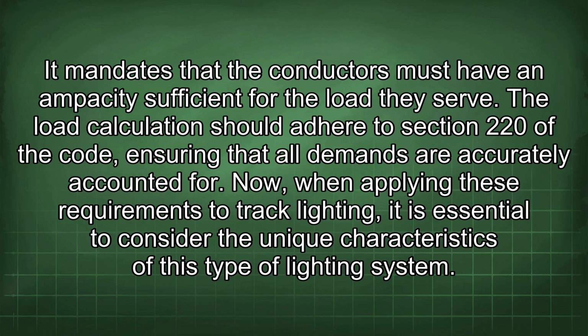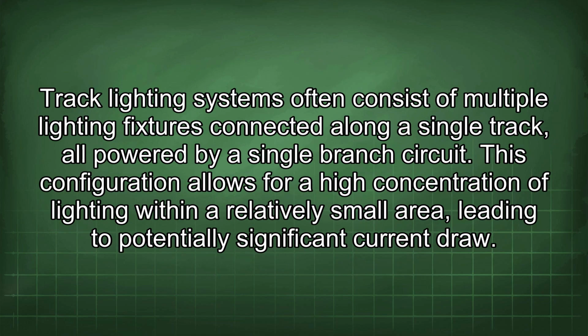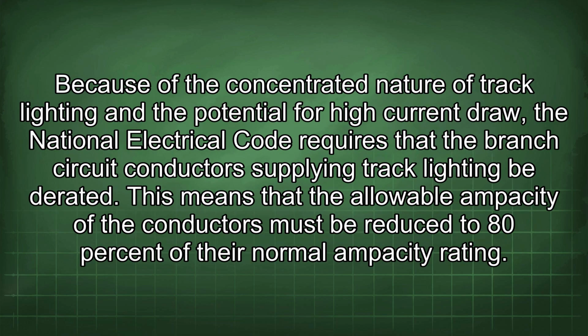Now, when applying these requirements to track lighting, it is essential to consider the unique characteristics of this type of lighting system. Track lighting systems often consist of multiple lighting fixtures connected along a single track, all powered by a single branch circuit. This configuration allows for a high concentration of lighting within a relatively small area, leading to potentially significant current draw. Because of the concentrated nature of track lighting and the potential for high current draw, the National Electrical Code requires that the branch circuit conductors supplying track lighting be derated.